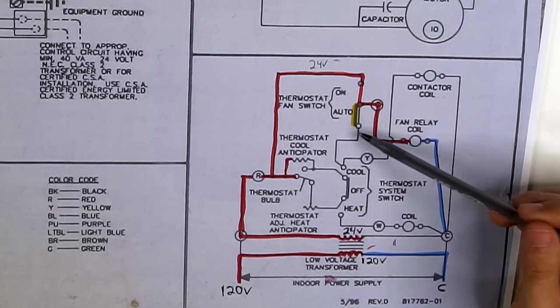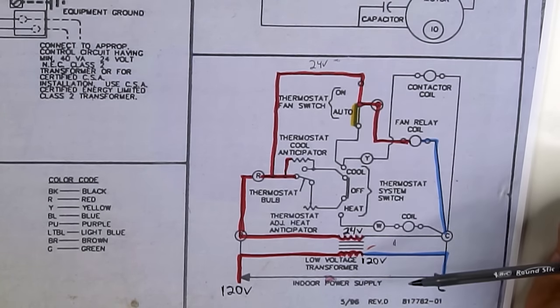This fan switch has nothing to do with the furnace or air conditioner — it simply controls the blower fan inside the furnace to either run 24/7 or stay on auto. When it's on auto, it only comes on when the furnace or air conditioner is running. Back where the power stopped: here's our power switch on the thermostat — it's currently on off. Then you have a cool setting and a heat setting with contact points. If you move this bar up it will turn on cooling; down will turn on the heat.